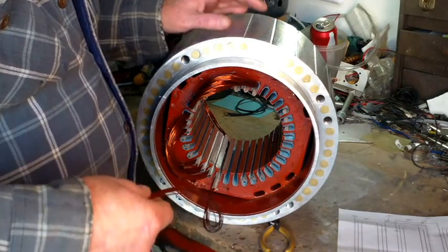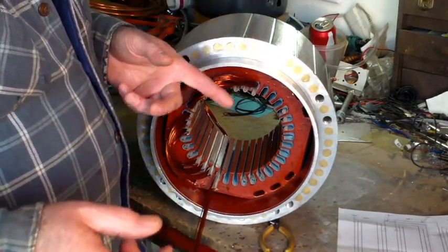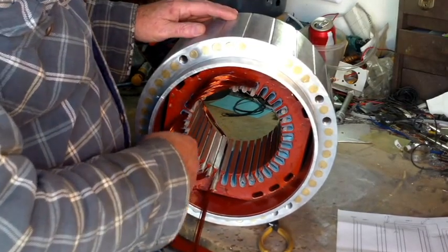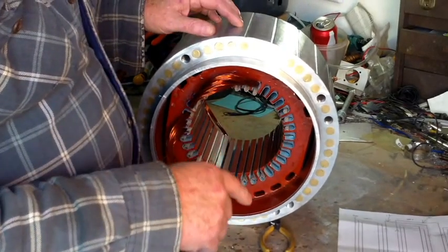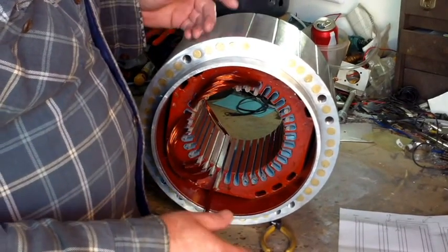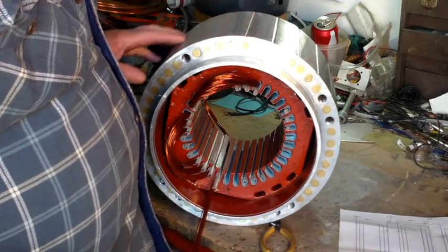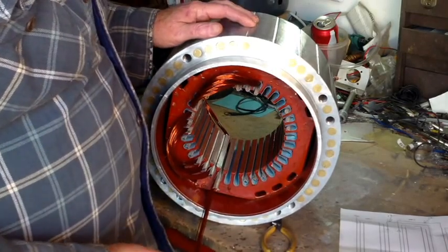How I figured out the length on my wires here — I actually just took one wire, a long wire, and I laid it in there. That will kind of give you some practice. If you just take one wire, lay in one pole, and then you can take that out and get the length of it times four. The red stuff here is spray insulation.